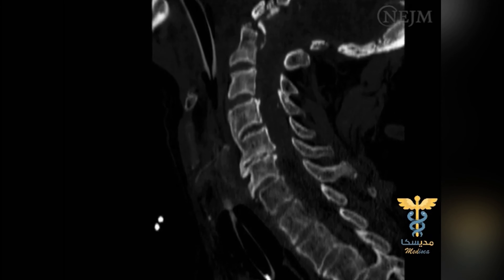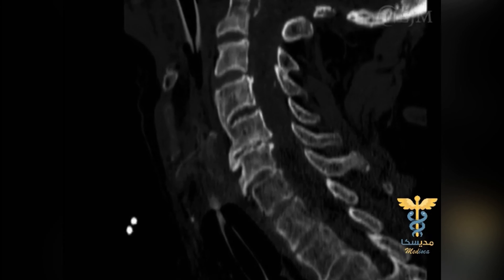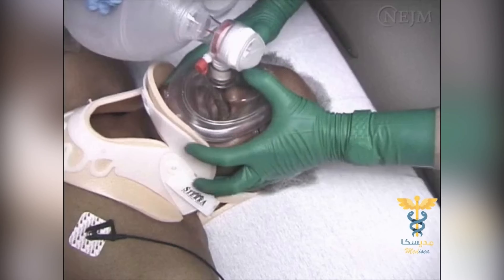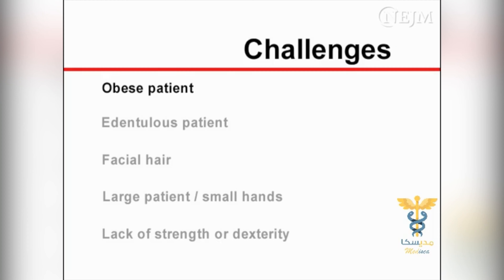The purpose of these reservoirs is to maximize the delivered oxygen concentration. A bag valve device's capability for delivering positive pressure ventilation should be tested before use. This can be achieved by sealing the bag valve device connector with the thumb and squeezing the bag with reasonable force. If it is difficult to compress the bag, or if air is forced between the connector and the thumb, positive pressure can be delivered.